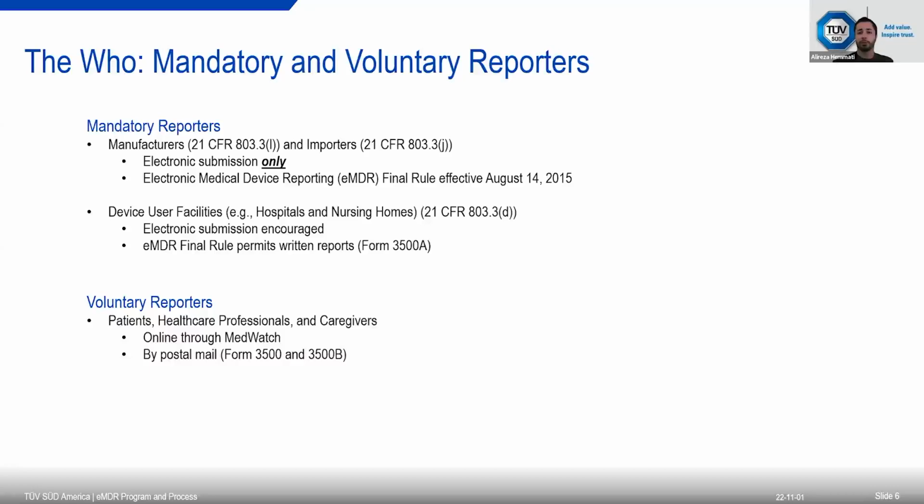Importer means any person who imports a device into the US and furthers the marketing of the device from the original place of manufacture to the person who makes final delivery or sale, but they do not repackage or otherwise change the container, device, label, wrapper, or package. Device user facilities are facilities like hospitals, nursing homes, and outpatient treatment facilities. However, physicians' offices, school nurse offices, and employee health units are not device user facilities.